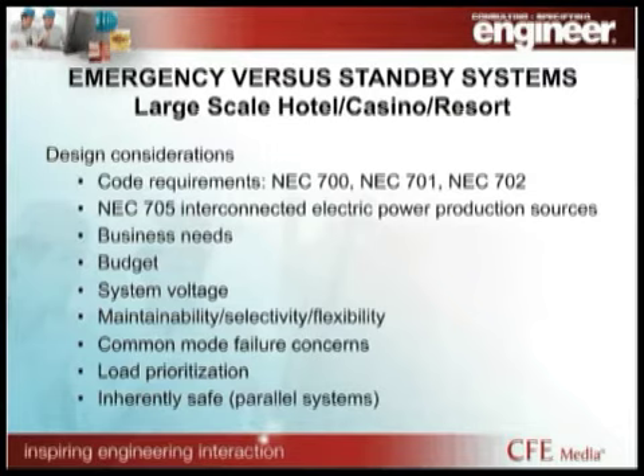System voltage is a consideration. If you're going to do bulk distribution for a large property, typically you're going to end up with 4160, 13.2, 12.47, some sort of 15 kV nominal, or 22, something in the less than 25 kV is what we've typically worked with. If you look at maintainability, selectivity, and flexibility in this system, one of the things you really have to focus on is how do we minimize and eliminate common mode failure points. When you go with an aggregate system, you don't want a fault on one bus to make the entire system collapse, because then the whole property is sitting in the dark. Load prioritization: legally required, emergency 700 is going to be Pri 1, your legally required Pri 2, and then all the priorities after that are really driven by what the owner expectation is for the property.